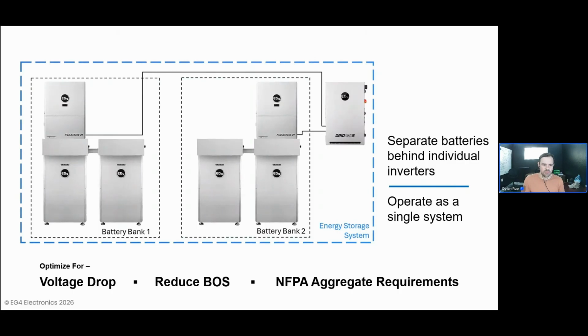However, a customer who wants 4 batteries to be deployed. So you can actually put 4 batteries on this site across 2 different locations in the home. And then you can simply run an AC connection from each inverter in the system over to the grid boss. You'll still run communication connections as well from the inverters over to the grid boss, and essentially have this entire system act as one large battery bank, despite the battery kind of being broken up into multiple sub banks behind individual inverters.